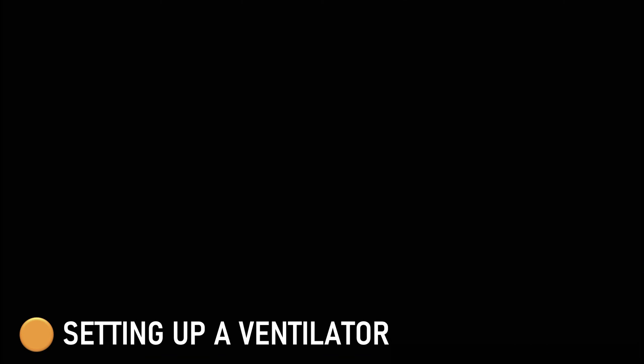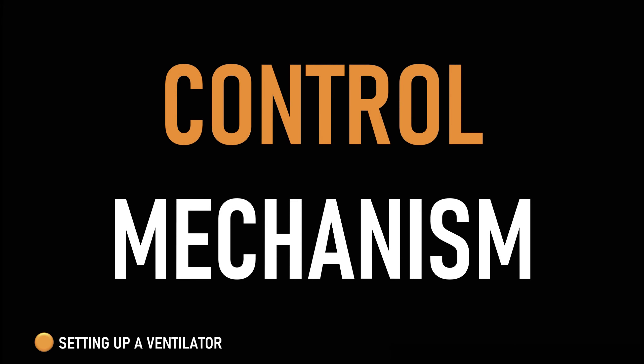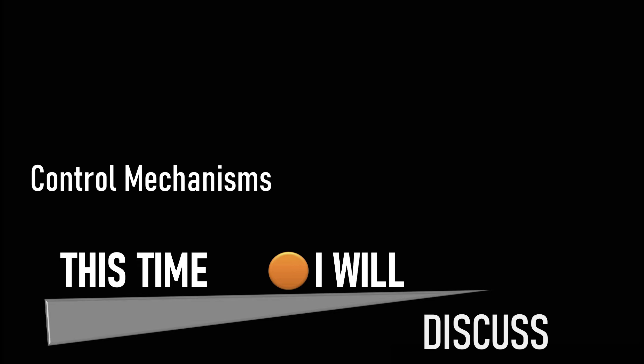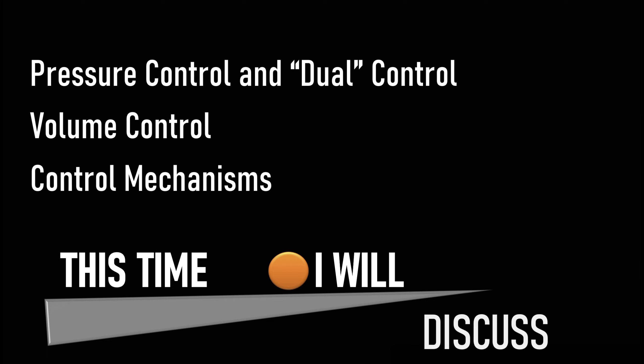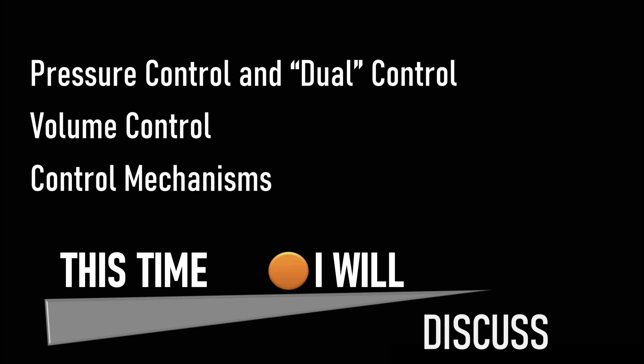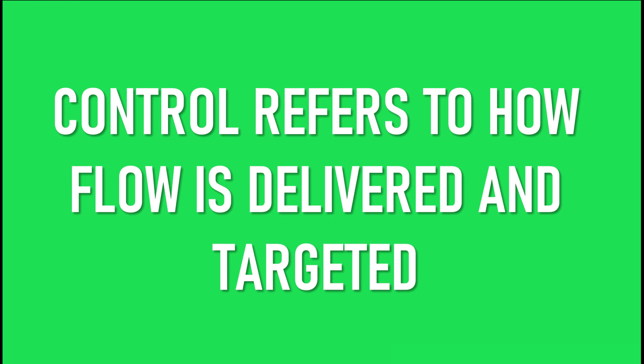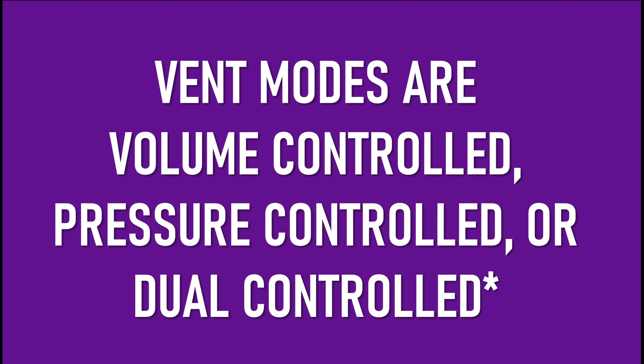So this is tutorial one: control mechanisms. I will discuss the different control mechanisms on mechanical ventilators, but they really fall into two generalized concepts. The first is volume control ventilation, where a tidal volume is given and the airway pressure is variable. Then there's pressure control ventilation, where the airway pressure is targeted and the tidal volume is variable. There is also a version known as dual control, which is volume guaranteed pressure control. The ventilator modes are volume control, pressure control, or dual control, and this is the first thing you need to decide when setting a ventilator.